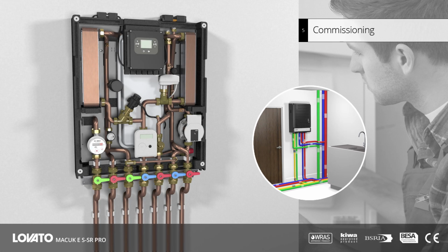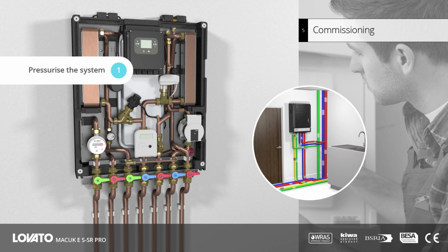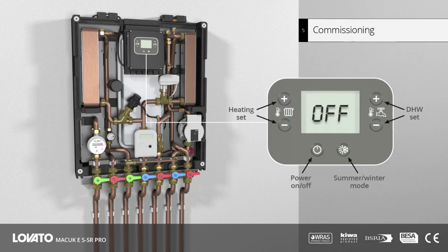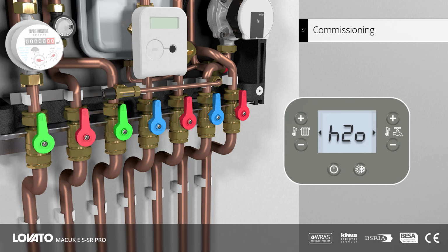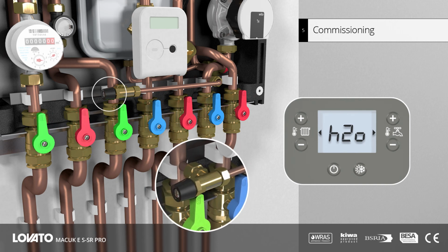Step 1 in correctly commissioning the Macuk E is to charge and pressurise the system. Firstly, press the power button on the control panel. Next, press the summer, winter and power button simultaneously, and using the DHW- button, navigate to the H2O menu. Open all shut-off valves and, via the filling loop, charge the system to the desired pressure.